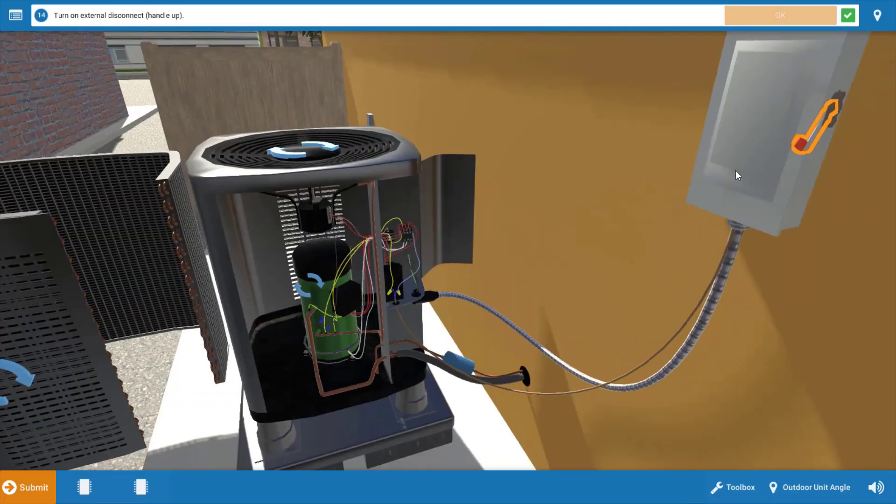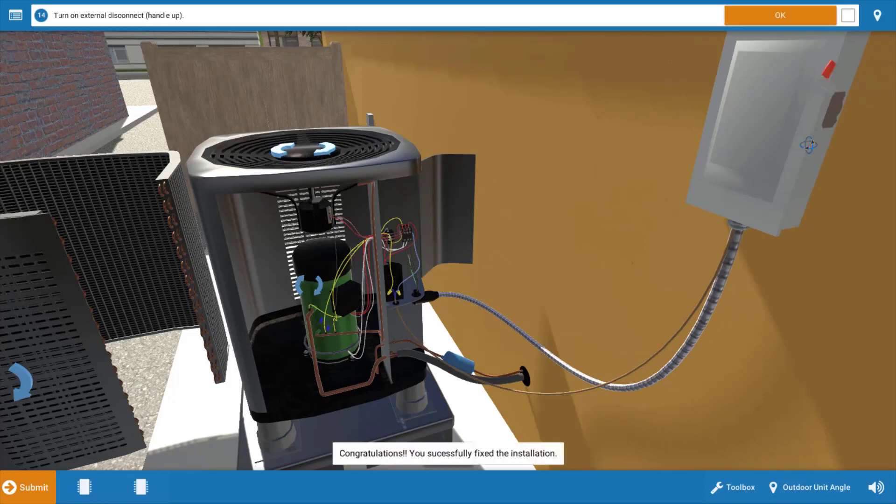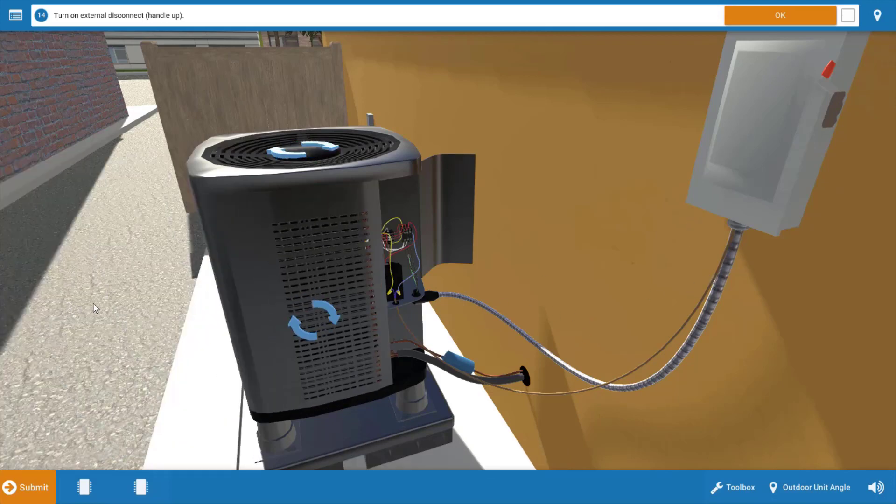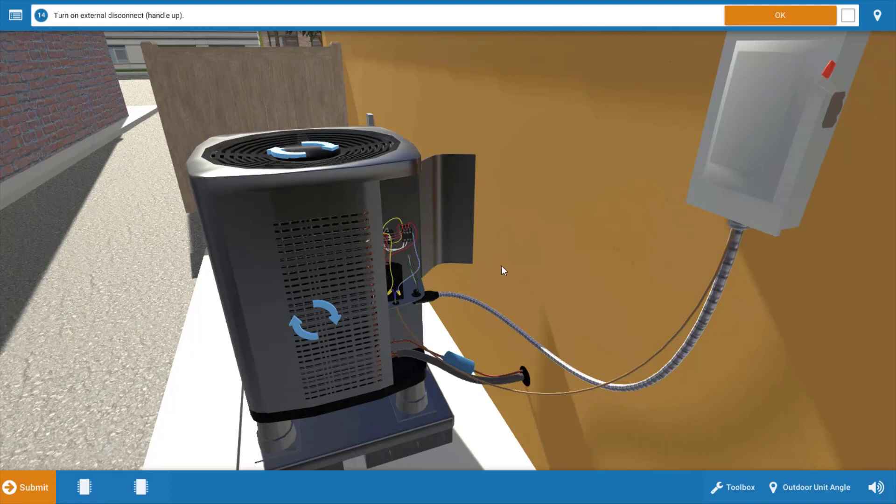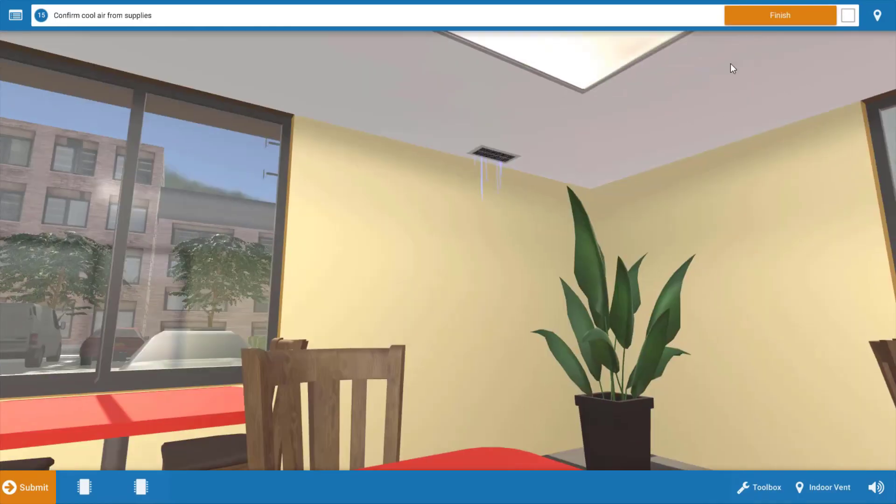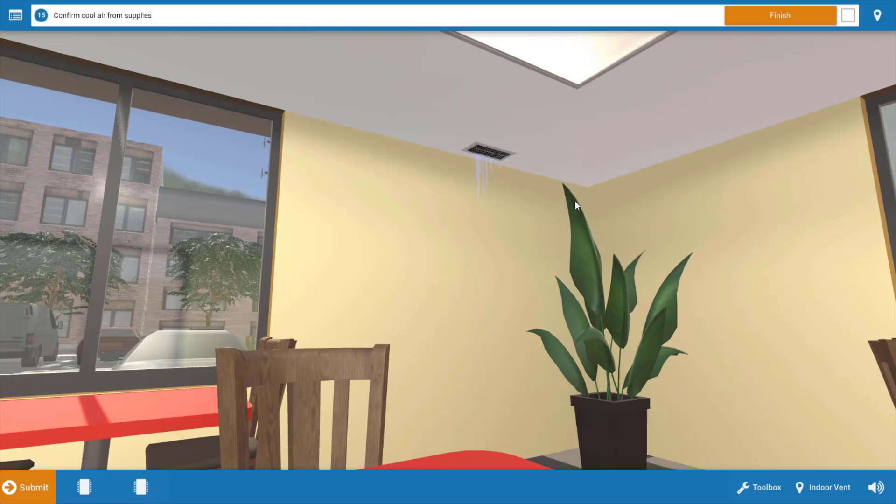Now, I would watch one full cycle of operation to ensure all loads are operating properly. But to start with, we're going to need to turn the power back on to verify this. And when we do this, everything comes back on. We put the cover back on the unit, close up the control panel, and we're ready to go here. Now, our last step would be to go up to the space and make sure the cool air is being received. And it is, as evidenced by this blue graphic out of this ceiling diffuser. I would also look at the filter and just change it if necessary to provide a little add value on the service call.